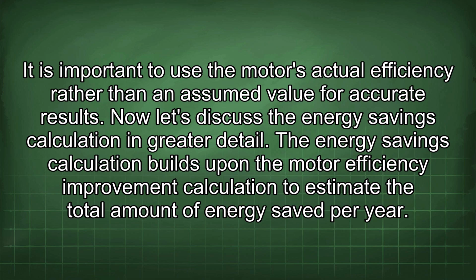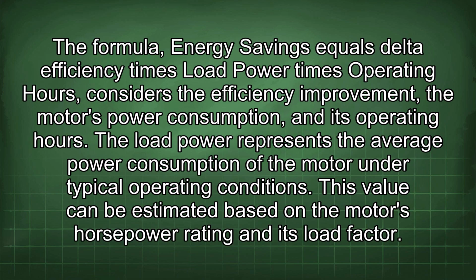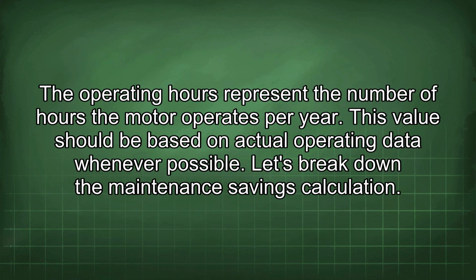Now let's discuss the energy savings calculation in greater detail. The energy savings calculation builds upon the motor efficiency improvement calculation to estimate the total amount of energy saved per year. The formula, energy savings equals delta efficiency times load power times operating hours, considers the efficiency improvement, the motor's power consumption, and its operating hours. The load power represents the average power consumption of the motor under typical operating conditions. This value can be estimated based on the motor's horsepower rating and its load factor. The operating hours represent the number of hours the motor operates per year. This value should be based on actual operating data wherever possible.